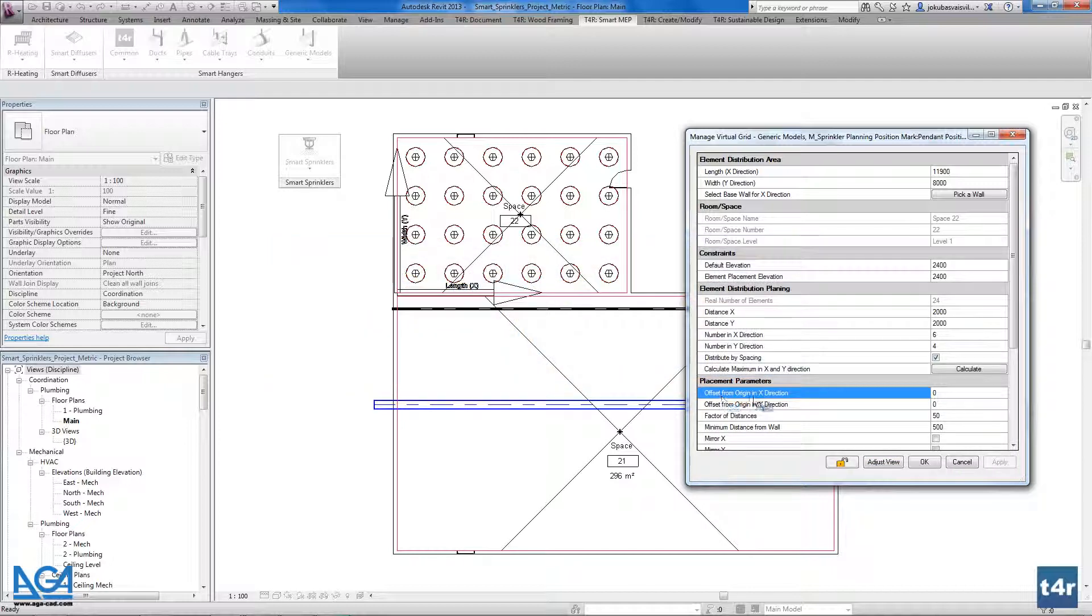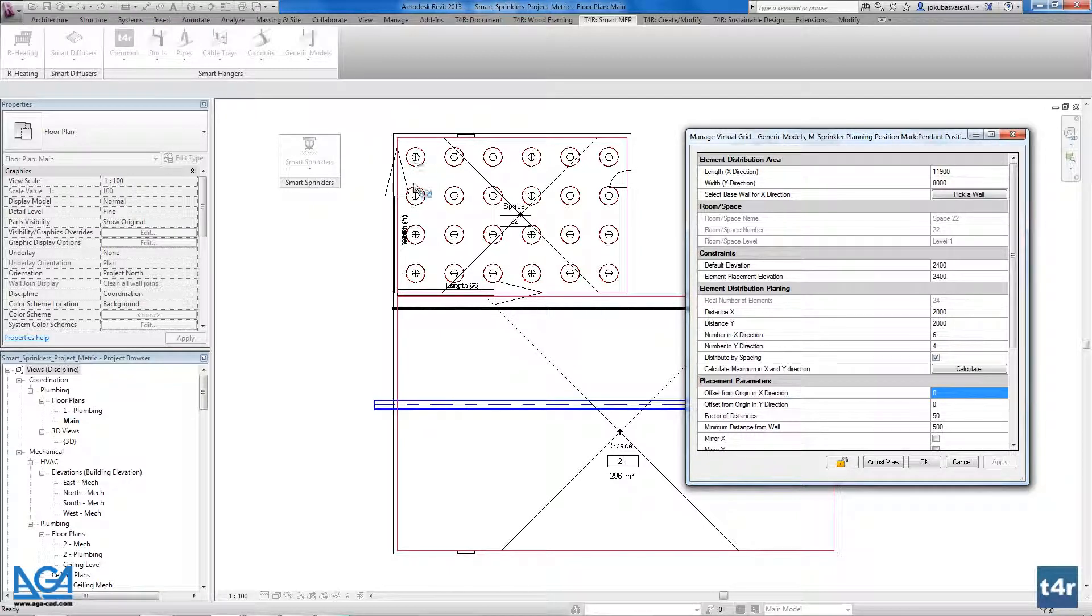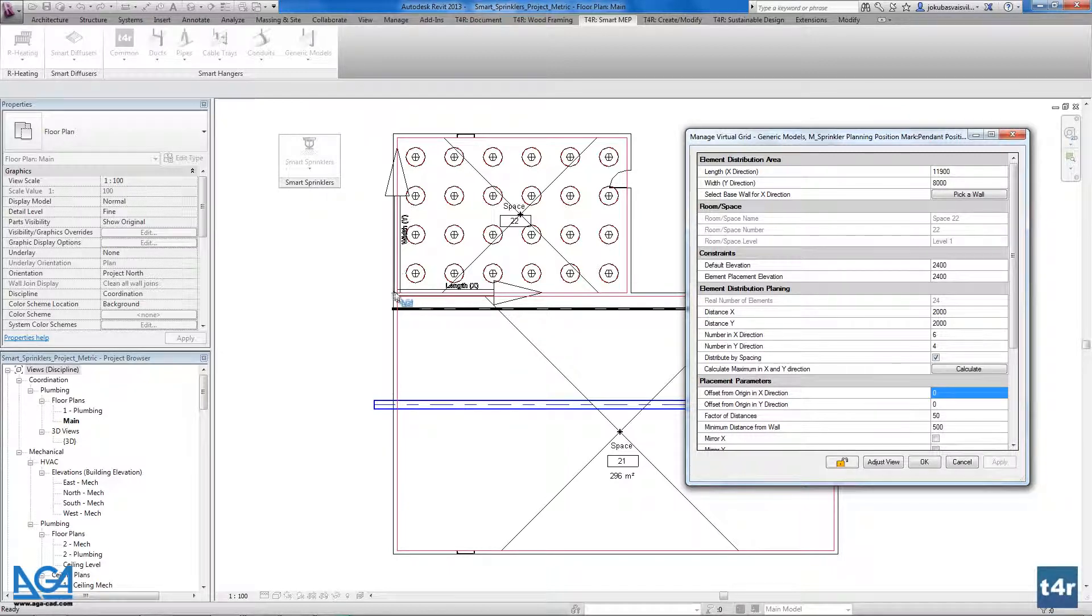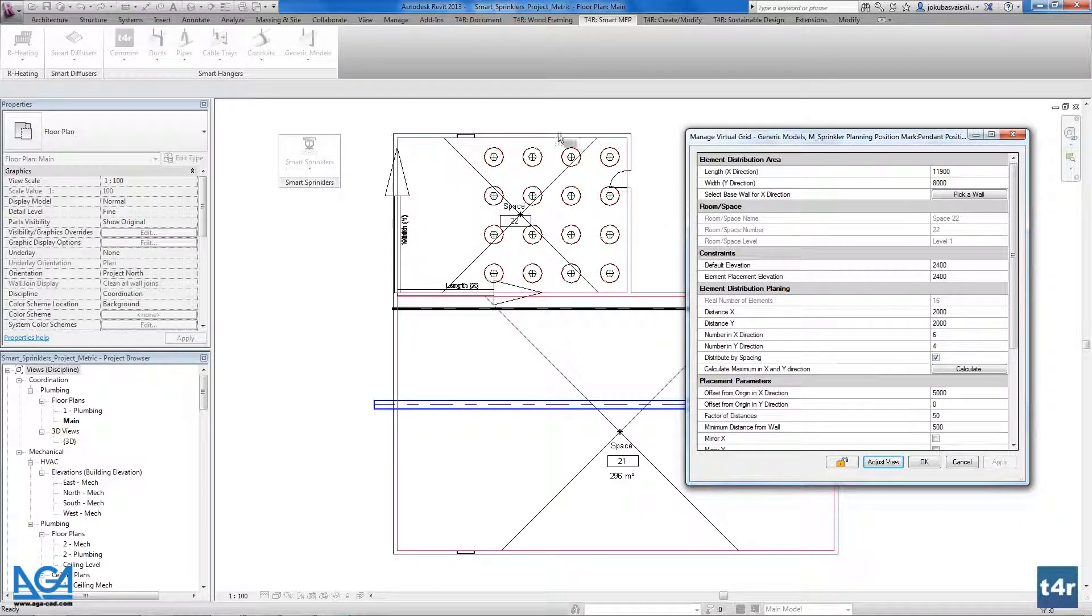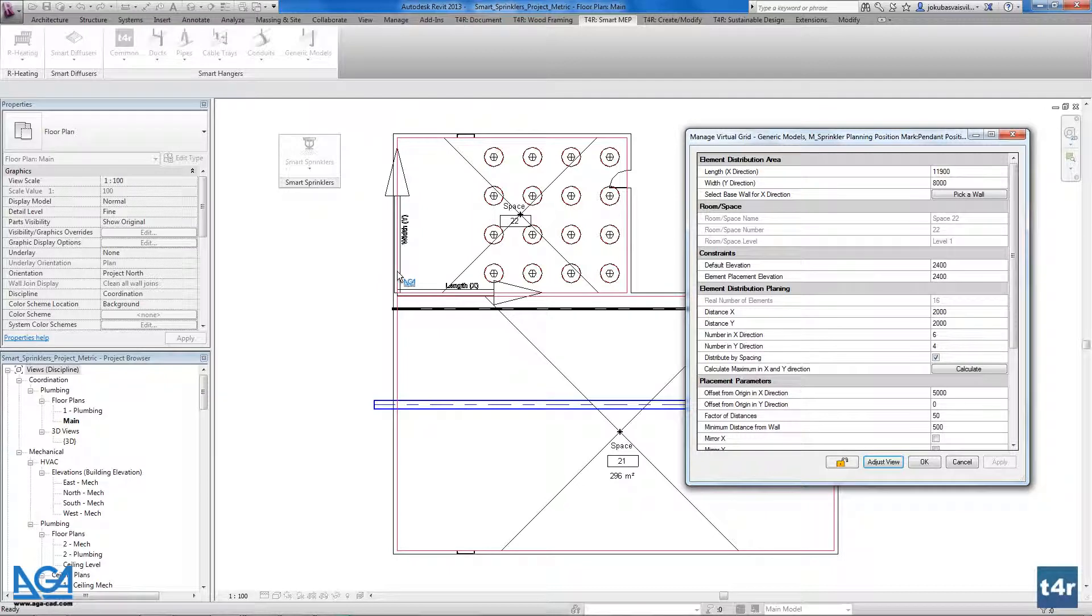Here we have the placement parameters. The offset from origin from X and from Y directions. For example if I want to move the first row from the X direction beginning at for example 5 meters, I could write it here. I could apply that function. And as you see we have from the sprinkler to the face of the wall we have 5 meters here.